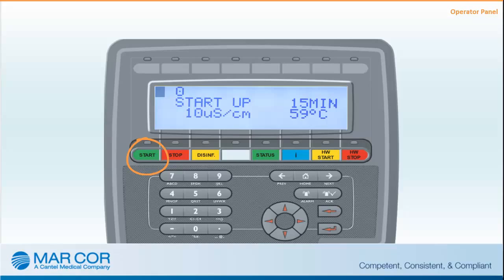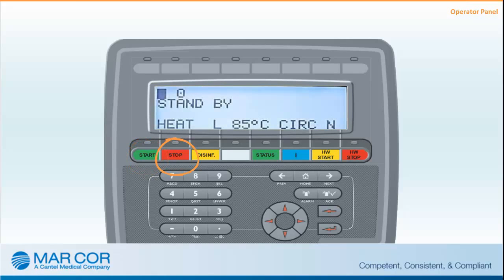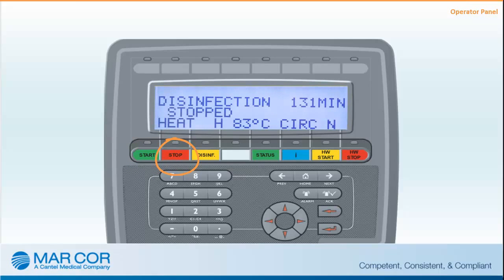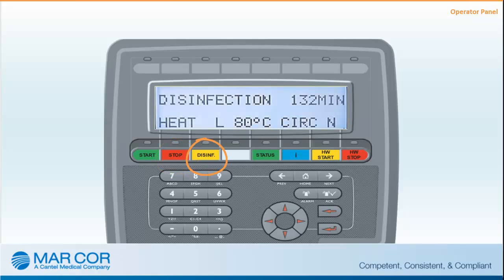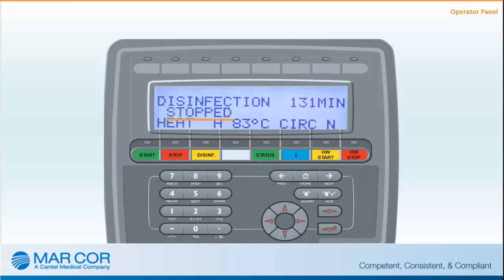The water diverts to the hot water tank until the temperature in the return line from the distribution loop is below 35 degrees Celsius. The Stop button stops the CWP and initiates a standby mode, and pauses the chemical disinfection cycle — the CWP unit stops and 'Stopped' flashes in the display. Disinfection cycles resume by pressing Disinfect. The Disinfect button starts the chemical disinfection cycle; remaining time shows on the display. 'Stopped' displays if the cycle is interrupted; to continue the chemical disinfection cycle, press Disinfect again.